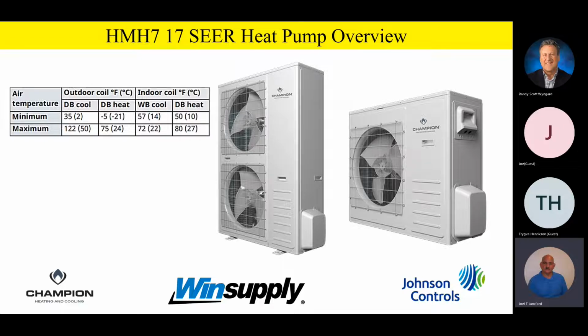And then the maximum operating temperatures are going to be dry bulb temperature outside, maximum 122 degrees for cooling, 75 degree for heating, maximum outdoor temperature. And then on the indoor coil, 72 degree wet bulb and then 80 degree dry bulb in the heating mode of operation will be considered normal operating parameters. And again, all this information that I've just spoken about, and there's the little tag there that you can see, the little text field that's available, you can read all about that in the install information. Any questions or comments so far before we continue?